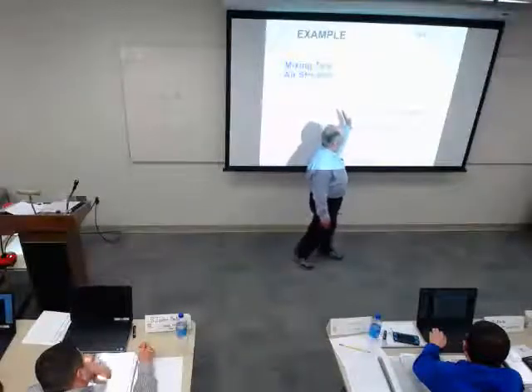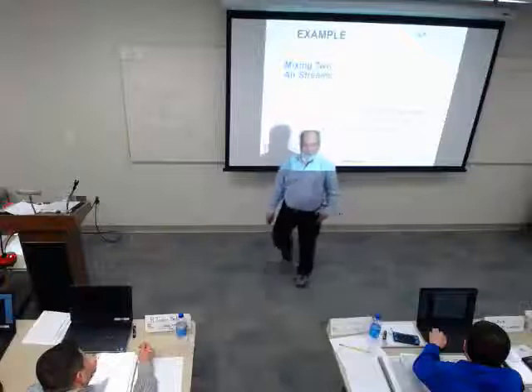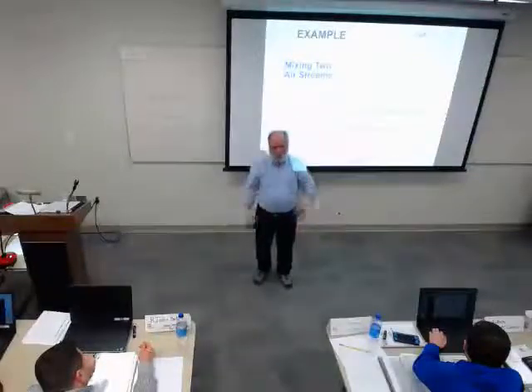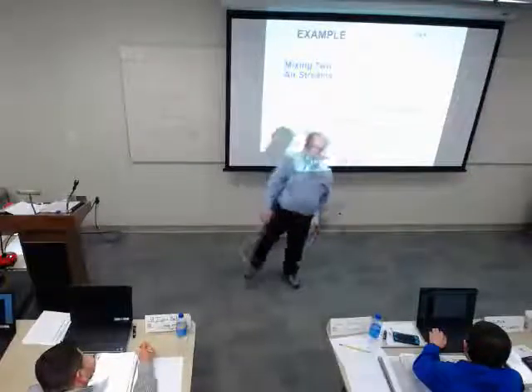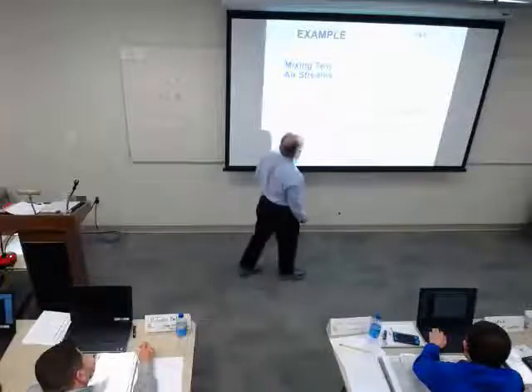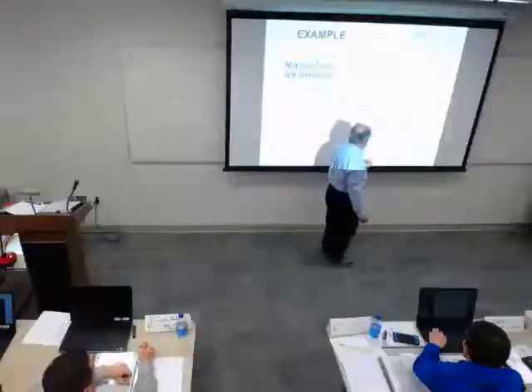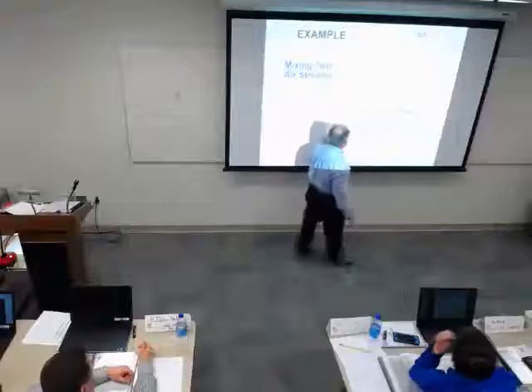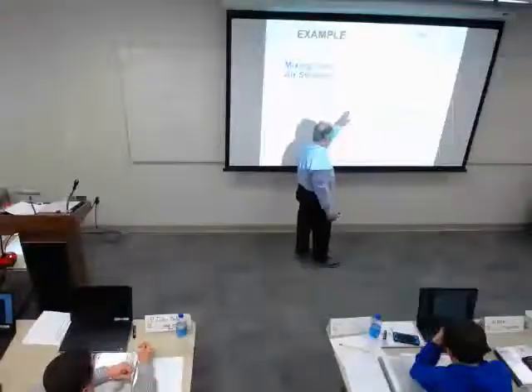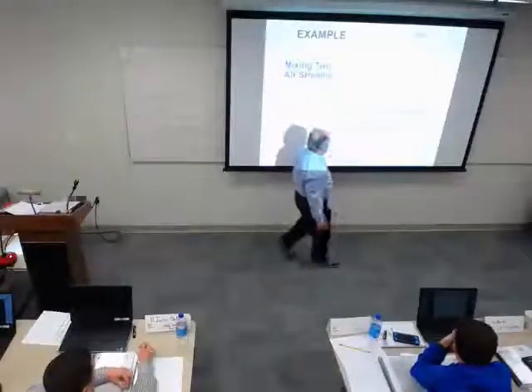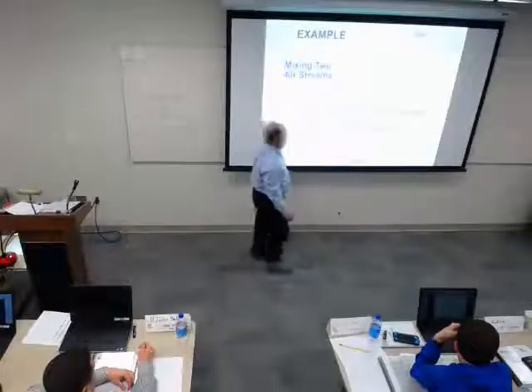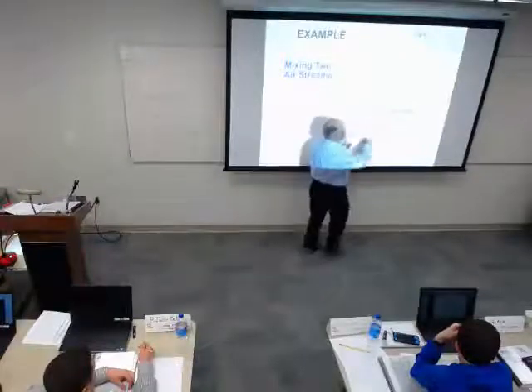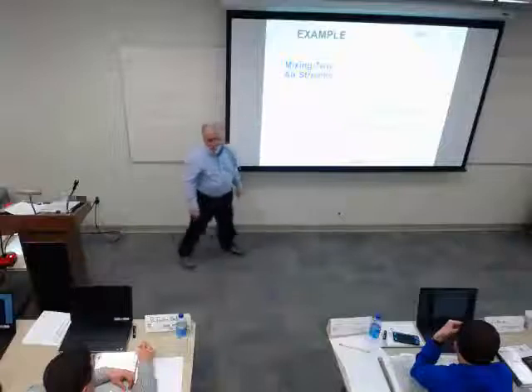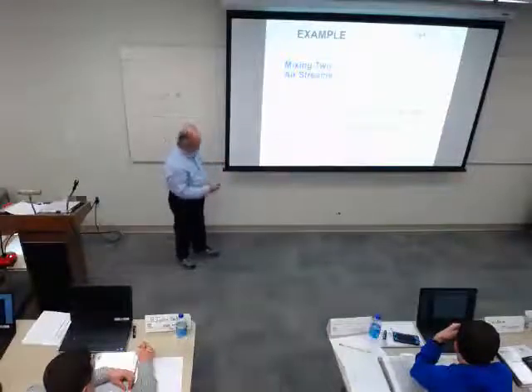And I wish we'd have done our psychrometric chart first, but the dry bulb lines are like this, and wet bulb lines are like this. Okay, so the dry bulb goes down there. They didn't draw the wet bulb line. Here's the relative humidity line, and here's another dry bulb line. They drew that one for us. And what we're going to be in here between these two points will be our mixed air condition.